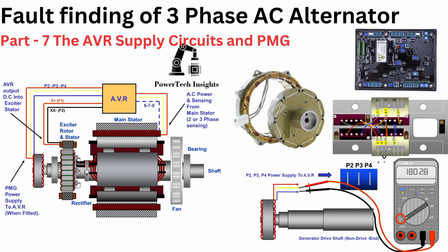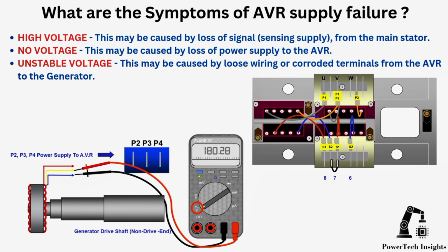In this part, we will provide a comprehensive guide on fault diagnosis for the AVR and control circuit and PMG. Possible symptoms of AVR supply failure. High voltage. This may be caused by loss of signal from the main stator. No voltage. This may be caused by loss of power supply to the AVR. Unstable voltage. This may be caused by loose wiring or corroded terminals from the AVR to the generator.